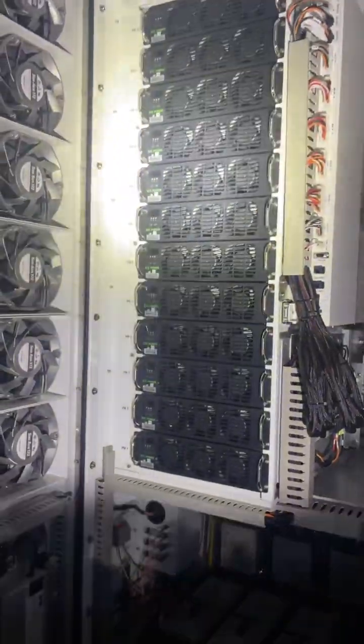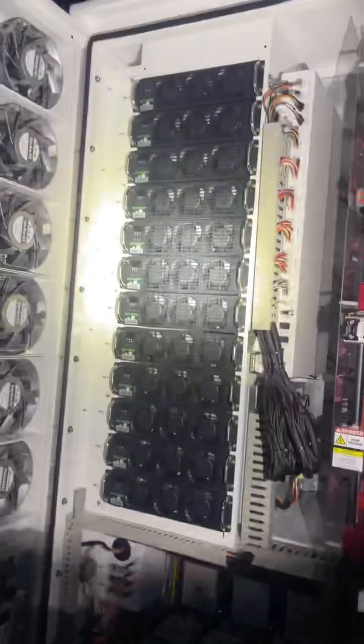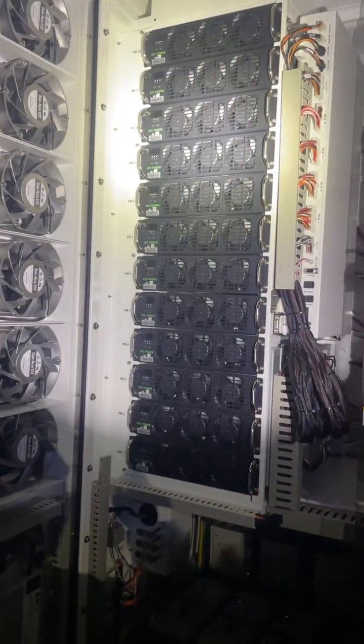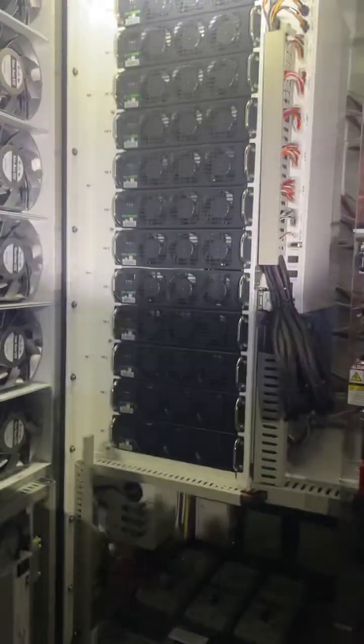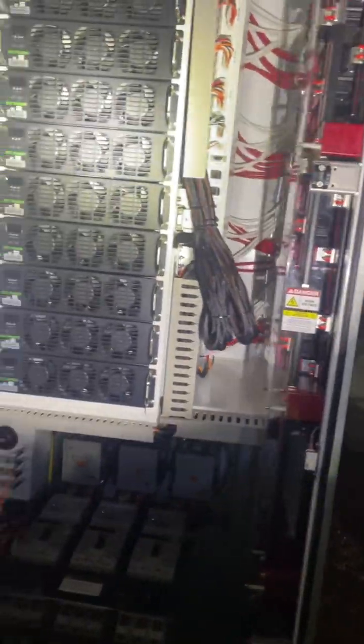So the 4 branch breakers are going to have the wiring fed underground to each power cabinet. Like I said, always open away from you. And these, all the brands are going to be a tad bit different, but they all have the same stuff. So these are your power modules: 2, 4, 6, 8, 10, 12. Not all of them have to work. And if some don't work, what that does is it doesn't allow this thing to charge as fast. It'll derate the charger over there.